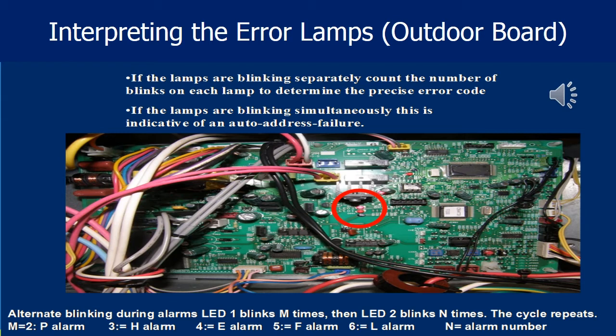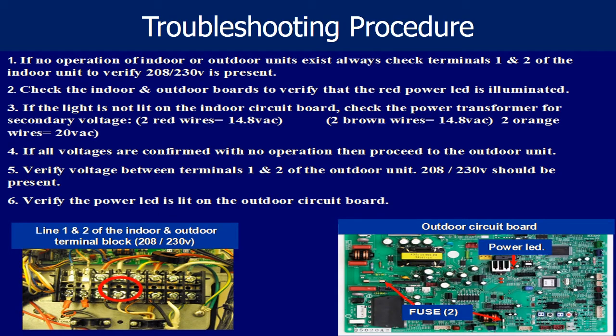LED number 1 can blink either 2 times for a P alarm, 3 times for an H alarm, 4 times for an E alarm, 5 times for an F alarm, or 6 times for an L alarm. After counting the blinks on LED 1, then count the consecutive number of blinks on LED 2 to determine the error code. For example, if LED 1 was blinking 2 times and LED 2 was blinking 4 times, this would represent a P04 error code.